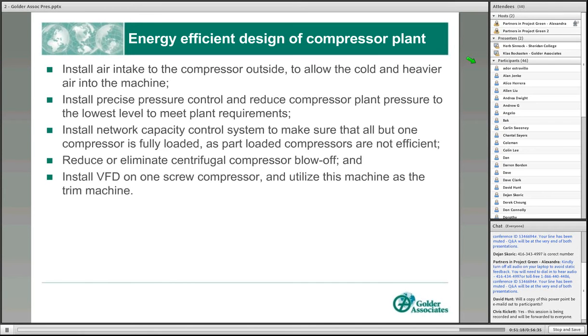The other one we spoke of earlier, which is precise pressure control, minimize the pressure differential as the system operates to be in the order of 1, 2, or 3 psi. The third one is, of course, network capacity control, where you have a control system that speaks to all 3 or 4 compressors and makes sure that you've got all compressors running full out, with the last machine being the trim machine, and that would be the only one modulating.